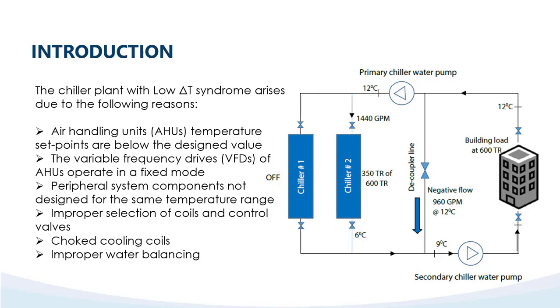Point number 2: the variable frequency drive VFD of the AHU operates in a fixed mode. This is happening in most hotels. The VFD is available for AHUs where the motor is more than 5 kW and is designed as VFD driven. However, it is not integrated properly, so the VFD works in a fixed mode. Point number 3: peripheral system components are not designed for the same temperature range — the high side and low side designs should match.